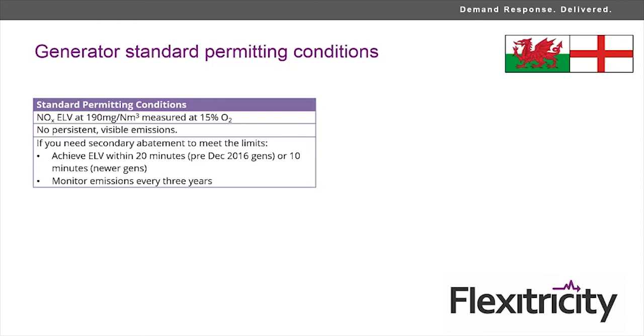Other things that come out: you mustn't be able to see the smoke, not for anything at the time - that's persistent visible emissions. And if secondary abatement, that is to say, if DeNOx kit is needed to meet those limits, then it's got to start reasonably quickly - within 20 minutes for old generators or 10 minutes for new generators, and they must be monitored every 3 years. So if it's an MCP, that is to say, if it's running over 500 hours, the MCP limits still apply, and furthermore, the requirements of that apply to generators - that's the minimum that must be complied with.